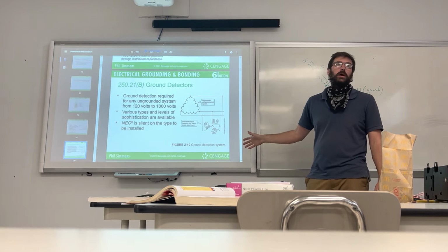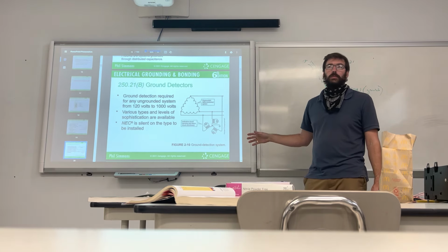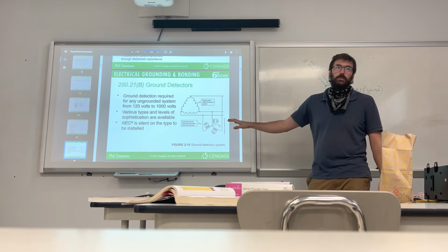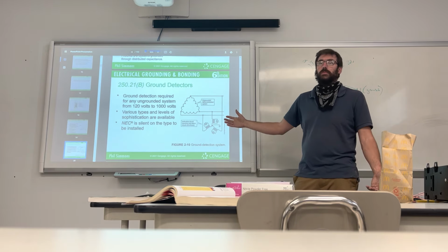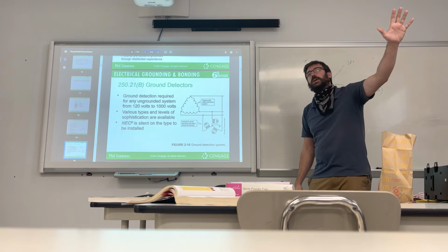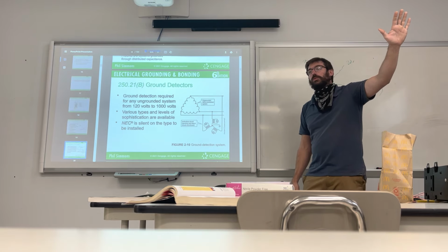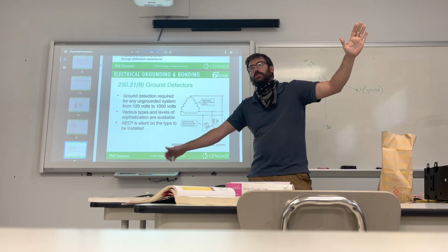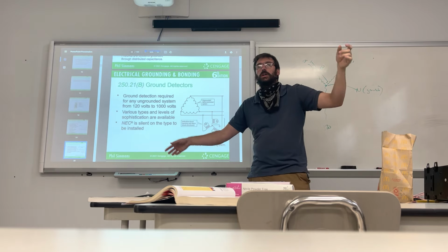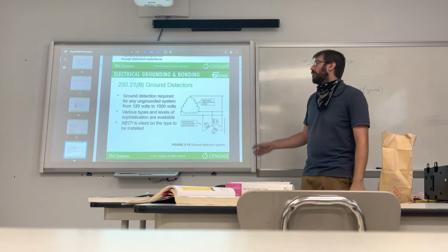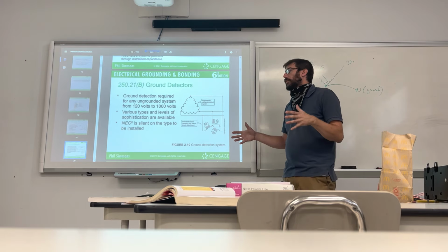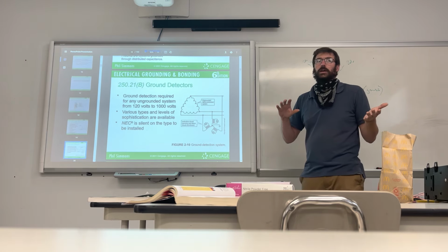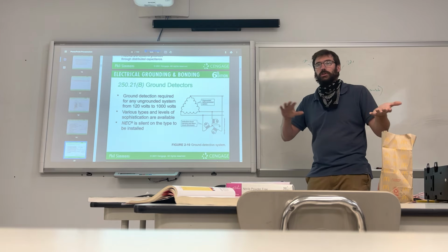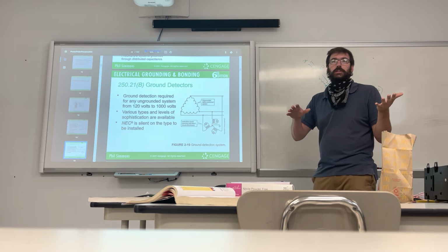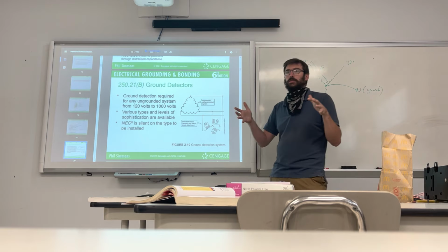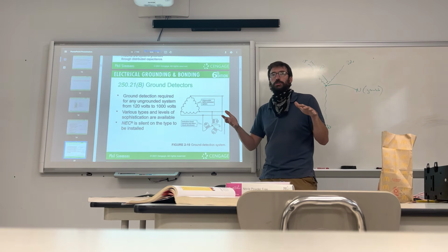live with power. You must have an alarm for this type of ungrounded system, because you can see how deadly it would be if you didn't. If you touch that hot piece of ungrounded metal, and you went and touched the door on your way out, and that door is touching concrete, that's grounded. Boom, you're going to get lit up. So they are very unsafe, but the danger is, you have to float it. You yourself being killed by that system, pretty bad. But all of Scranton losing power or water, also pretty bad.